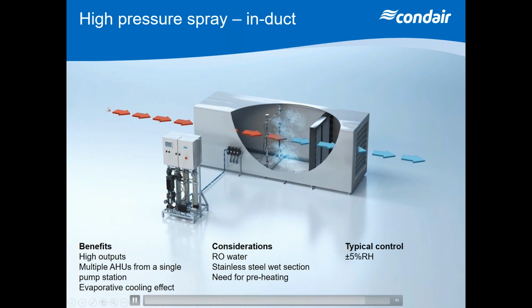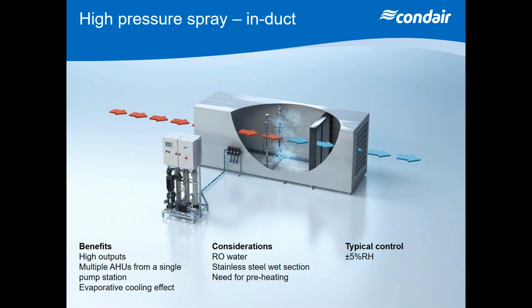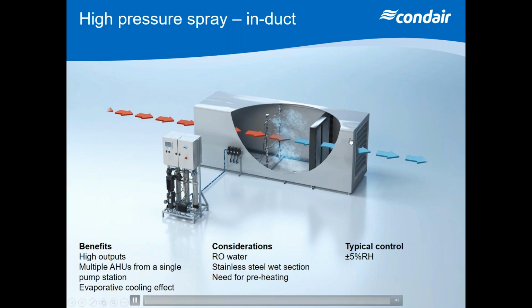There are some things to consider though. Of course, I'm going to be using RO water. And as soon as we do that, we're using twice the amount of water, because you put 100 litres in, 50 litres will go to the RO, to the humidifier, and 50 litres will be flushing the RO membrane. So you're using more water. And you've got a mist eliminator there to prevent any moisture going into the airflow. And also you're going to require a stainless steel section in that air handling unit, because it's a wet section. So you're going to have a stainless steel section with a drip tray. But because we're modulating via turning on and off various rows of this manifold, I will get plus or minus 5% RH control. And with this unit, I can control up to 4 air handling units from one system.